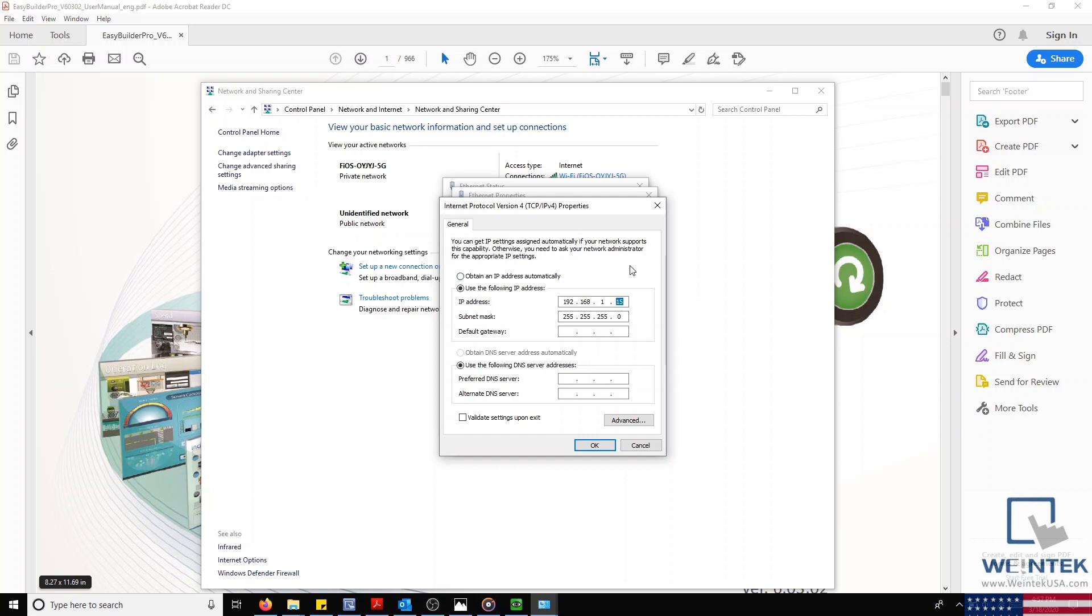To keep things simple, our subnet mask should match the subnet mask of our HMI. So in here, I'll click on this, and the system should automatically enter 255.255.255.0. After which, we can leave the rest blank, since we're just preparing a direct connection from our PC to the HMI.